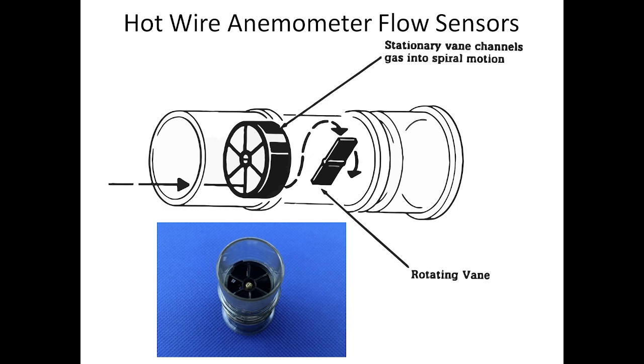Now this is an older style one. I do believe that this one here is a GE, and the way this one works is the air comes in, it goes across a spiral grid, and these vanes create turbulence, which then creates a conical airflow, and that spins a rotating vane, and that rotating vane is what's measuring the amount of airflow. Now this one here has moving parts. Notice many of these flow sensors do not utilize moving parts because moving parts equal problems. They always equal problems. So that's why flow sensors that require no moving parts are better.